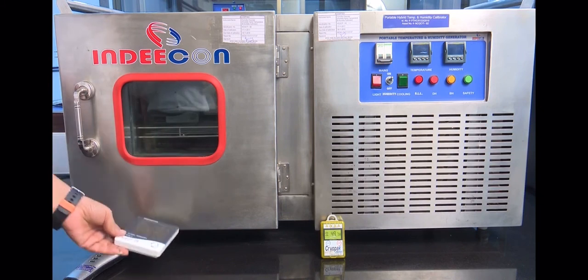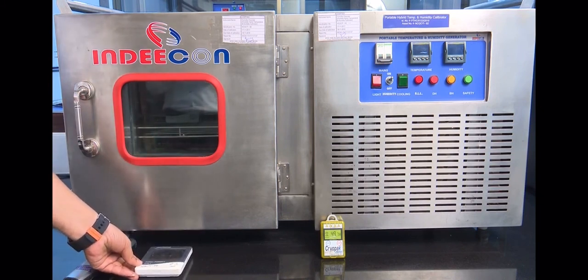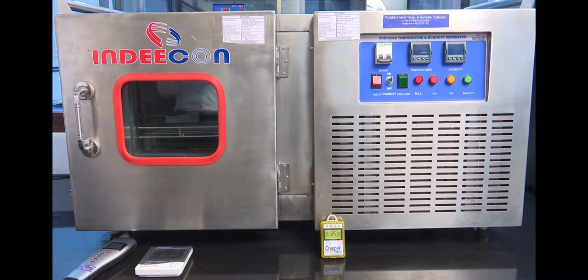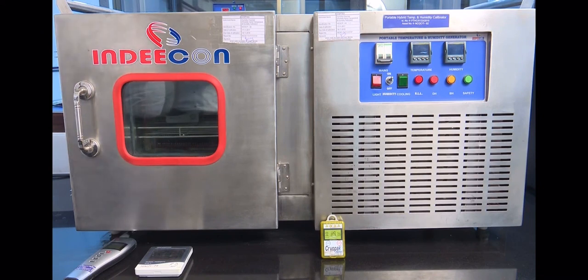Now I will demonstrate the calibration of digital thermohygrometer. As per calibration method, for calibration of digital thermohygrometer, we need to select 5 calibration points of humidity and temperature range as approximately 20% RH, 40% RH, 50% RH, 80% RH and 90% RH, and 10 degrees centigrade, 25 degrees centigrade, 30 degrees centigrade, 40 degrees centigrade and 50 degrees centigrade of the range of unit under calibration.